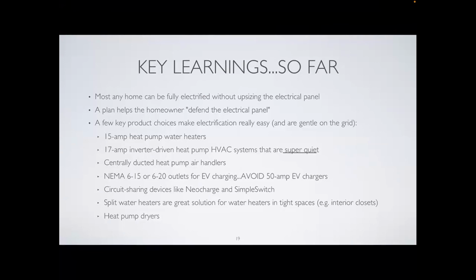We're also seeing that there are a few key product choices that really make electrification very easy: 15 amp water heaters, these low amperage inverter-driven HVAC systems that also happen to be super quiet, and centrally ducted heat pump air handlers, like I showed you, not the mini splits that go into every room, which can be more expensive. This just swaps right into where your furnace is, so you don't have to run as many refrigerant lines throughout the house. It's just one refrigerant line run to where the furnace used to be.